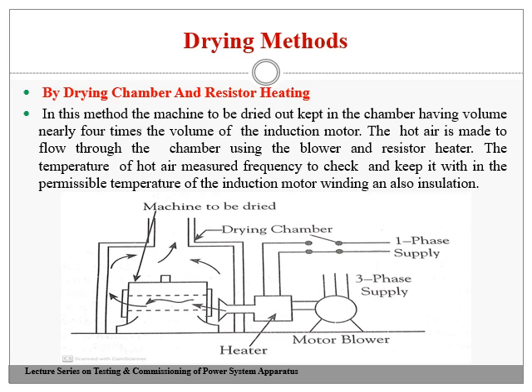Here we take the induction motor, remove either end rings of the induction motor, and keep it in the heating chamber. Then, using the heater, which is supplied by a single phase supply, we heat this heater. Once it gets heated up, we blow air across the heater so that the air gets heated up. That hot air is allowed into the chamber, and when hot air moves inside the motor, it removes all the moisture content which might have been entrapped or absorbed by the insulation, and which will be let off. That's why we say that proper ventilation is to be provided.